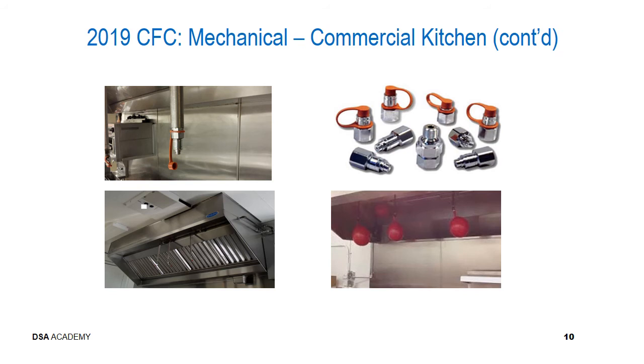Here are some components of the fire extinguishing system for a commercial cooking hood. In the upper left, we see the nozzle with the protective grease cap. Then below that, the hood itself with the piping visible to the drops. The upper right, the various types of nozzles. And in the lower right, what is commonly referred to as the balloon test. The balloon test verifies that equal distribution of pressure when the system is activated occurs.